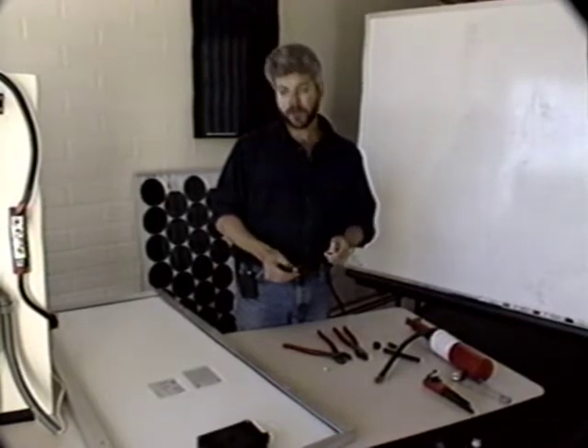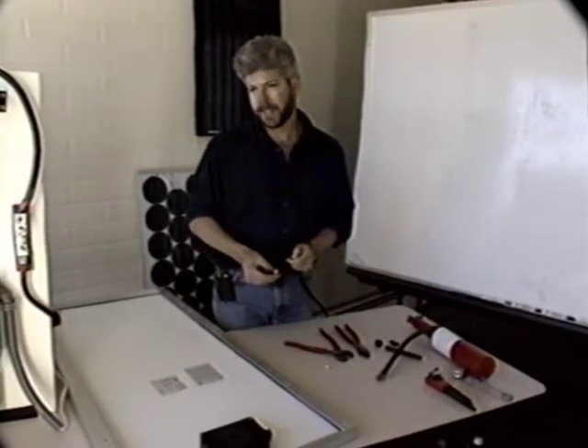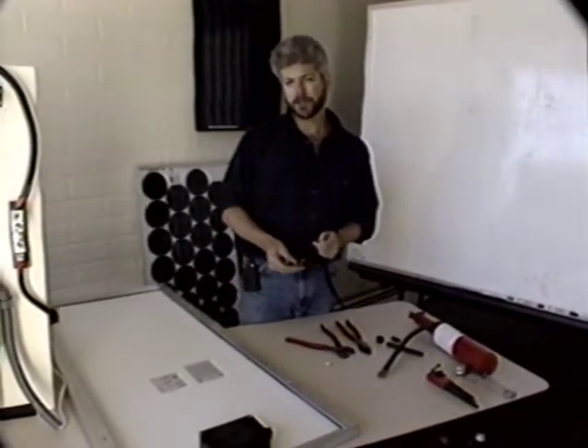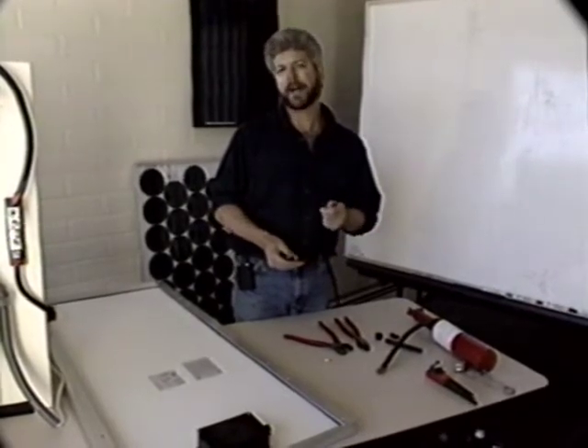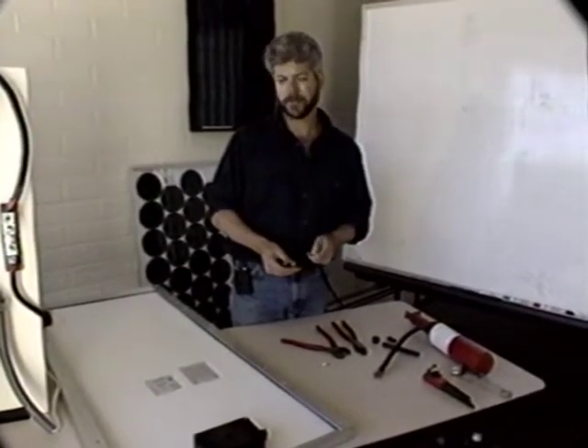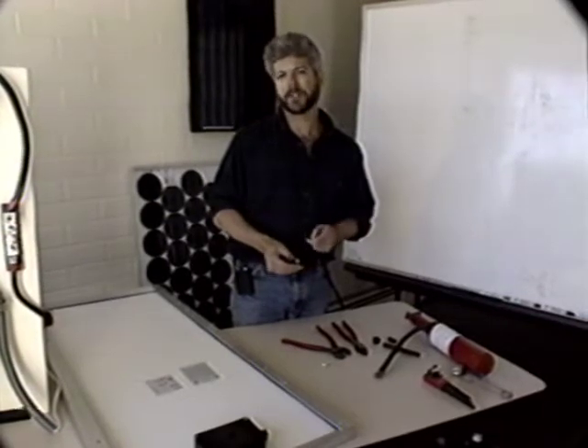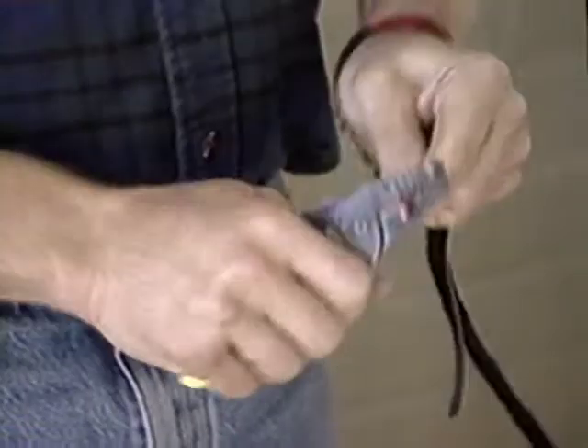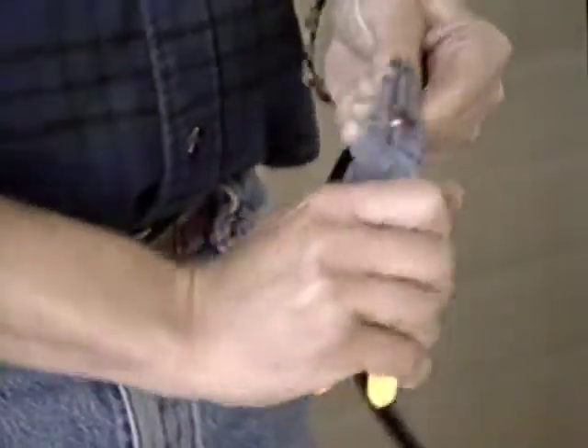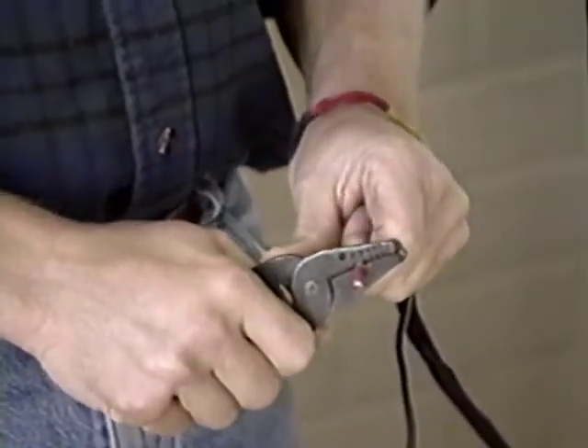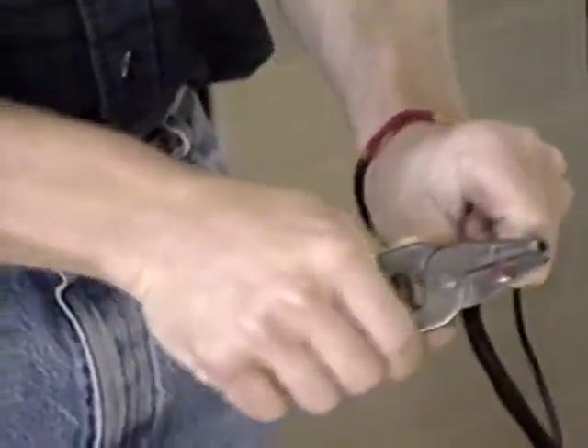Let's talk about one of the most important connections, the connection right in the module junction boxes to the wire that runs from the solar collectors down to the power conditioning equipment. This is a number 10 copper wire that's rated for outdoor use, so we can use it outside.